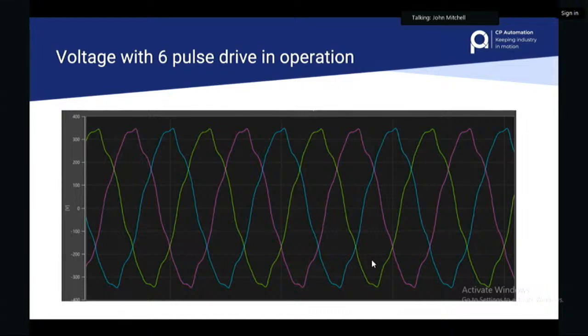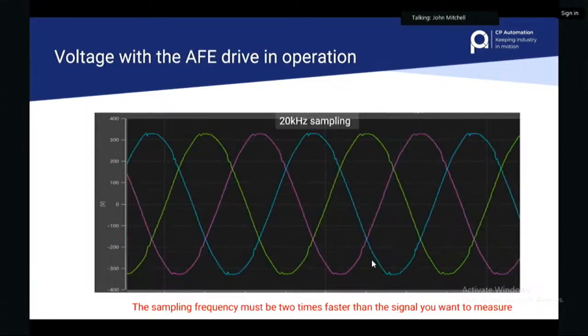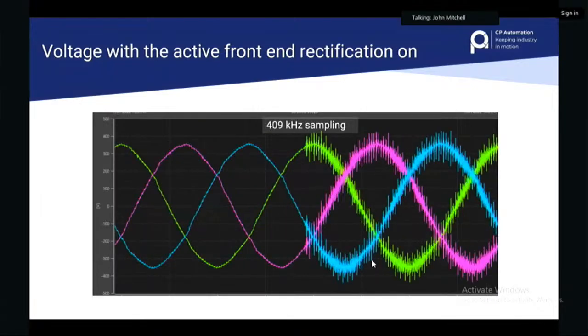So here you'll see a voltage of a 6-pulse drive. If you don't have a meter that's fast enough, this is what I was talking about, buying the right kind of power quality meter to measure and analyze with a high enough sampling frequency, you would mistakenly see that AFE drive, the active front-end drive, looking like this. And to the naked eye, that looks like a perfectly good signal to me. The problem is it actually looks like this. So when you have a frequency sampling rate in the processor high enough to measure what's going on from the drive, you can actually see that all of those switching transients are going through the signal. And I have cases to show you this shortly.